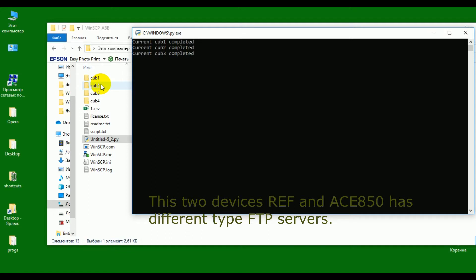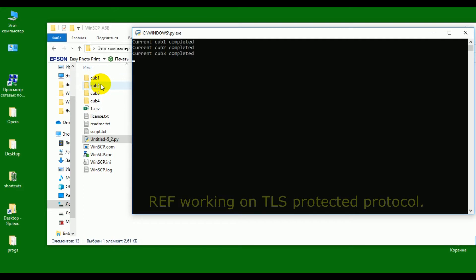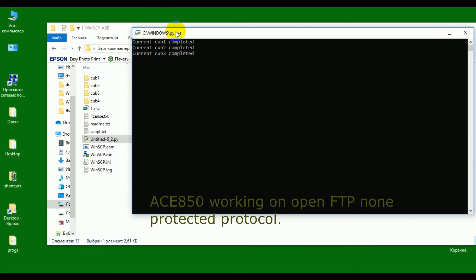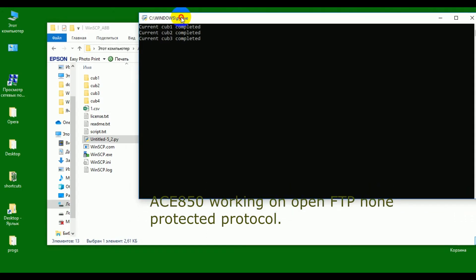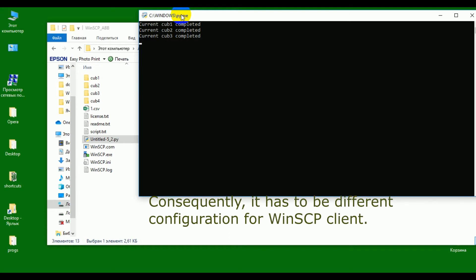These two devices — REF and ACE850 — have different FTP servers. REF works on TLS protected protocol, while ACE850 works on Open FTP non-protected protocol. Consequently, they require different configurations for the WinSCP client.